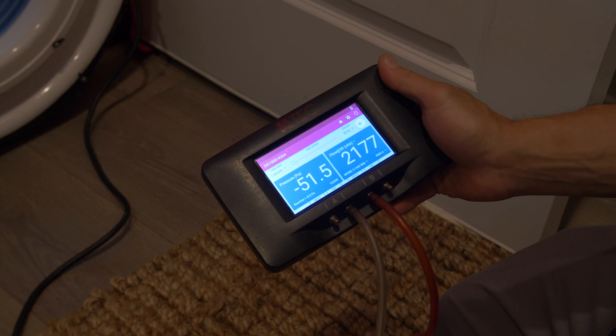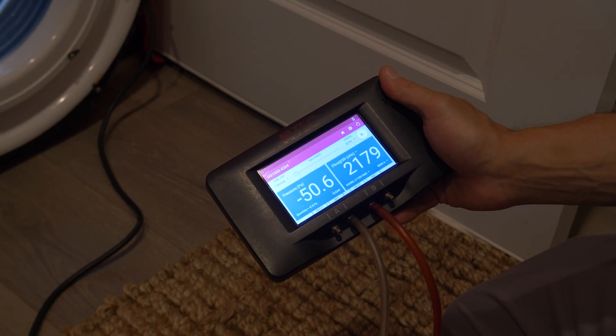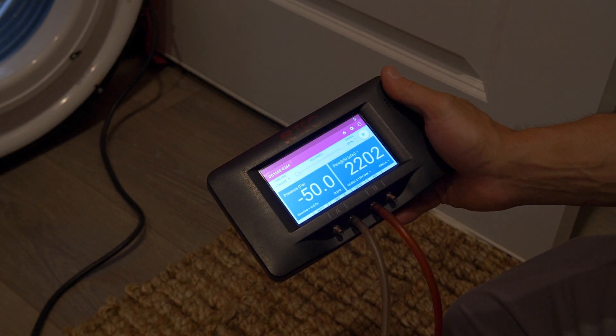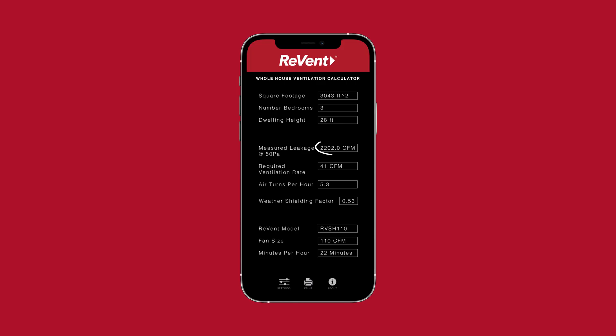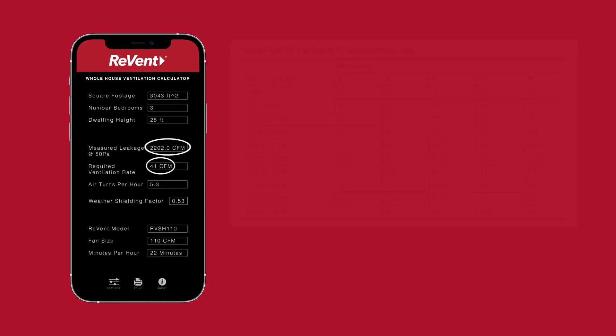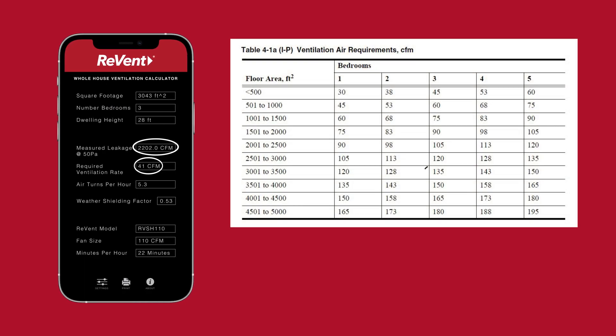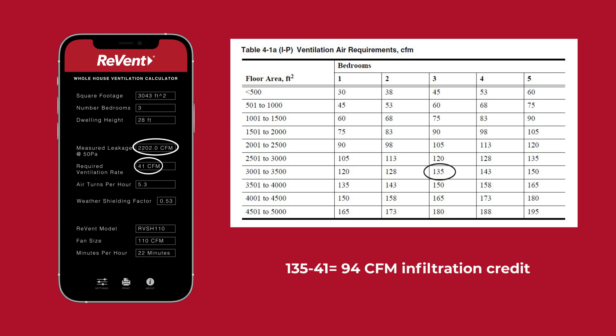For an example, our blower door test results read 2,202 CFMs at 50 pascals. We plugged this into Revent's quick calculator app and determined that the correct amount of ventilation was 41 CFMs. ASHRAE's chart states that the ventilation requirements of the exact same home are 135 CFMs. So by conducting a blower door test and using Revent's quick calculator app, we were able to take a 94 CFM infiltration credit.